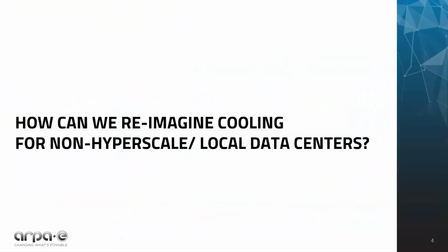If you think about it, computer chips typically run at 60 to 90 degrees Celsius. Since ambient temperatures are much lower than that, heat should flow naturally from hot to cold — this is the second law of thermodynamics. So why do we need to use energy for air conditioning in the first place? Why do we need air conditioning, which is a heat pump, to cool these data centers? Can we reimagine cooling for these 5 categories of data centers so that they no longer, or barely, require air conditioning at all?